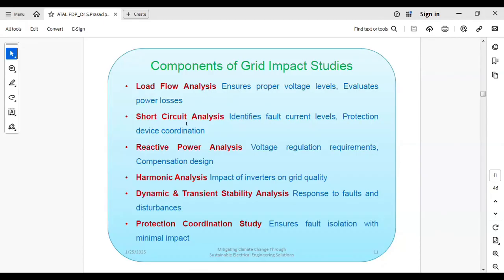Then the next important study is short circuit analysis. I will discuss each and everything in detail by considering a practical case study, and I will explain how things are happening. Short circuit analysis is needed when we are integrating a PV plant to the grid. Suppose a short circuit happens: a three phase short circuit, a line to ground fault, a double line to ground fault, or a double line to line fault. If these types of faults happen, what is the maximum short circuit current that will flow to the PV system? What will be the fault current contributed by the grid, and what will be the fault current contributed by the PV plant?